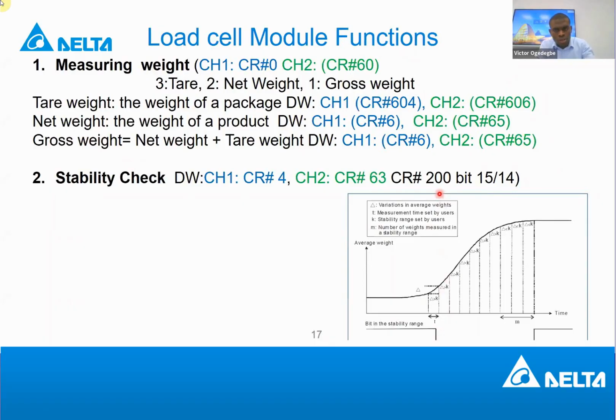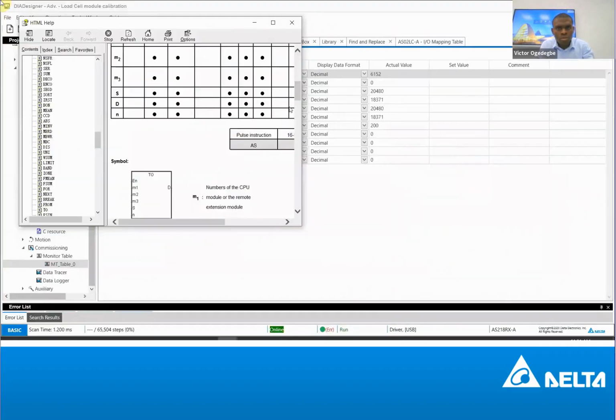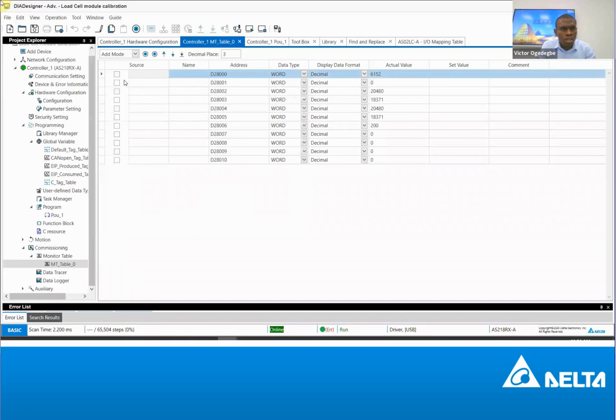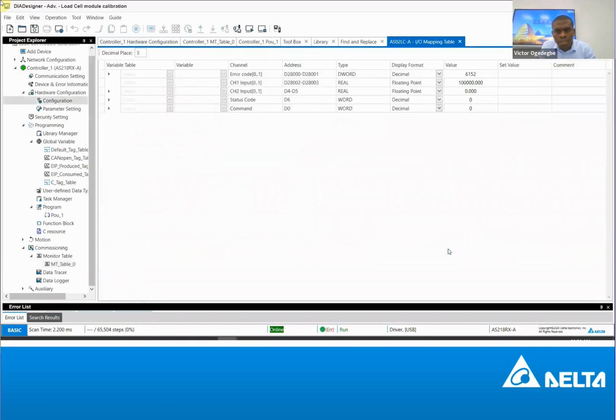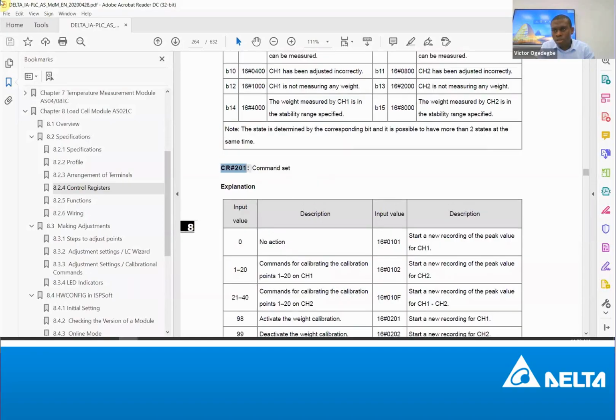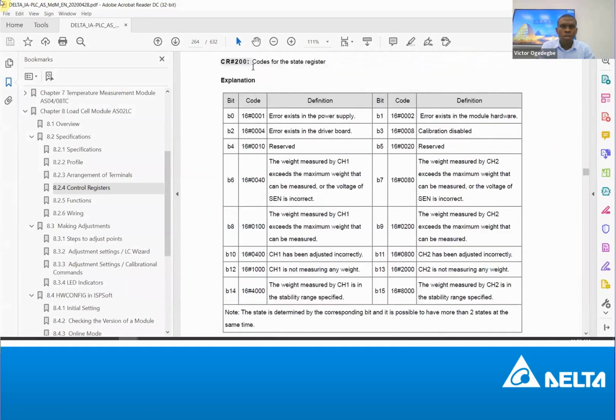In the case of our configuration, if I switch to our program, if you come to hardware configuration, if you go to that place again, the status is state code. This is a 16-bit register. If bit 14 is high, for example, it means that channel 1 measurement is at a steady level, is stable. Besides this, I also showed you that there's a control register 200. You can also see it in control register 200. I think I'm here. Yes, good. This is the command set. If you don't use this, because this is being mapped by the CPU, you can use it to and fro to get this control register 200.